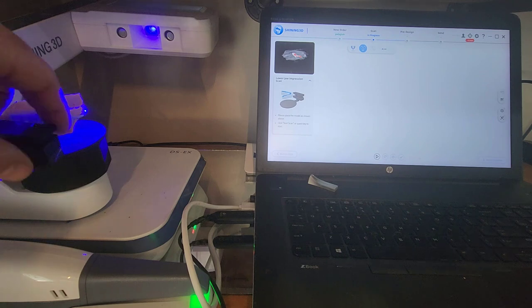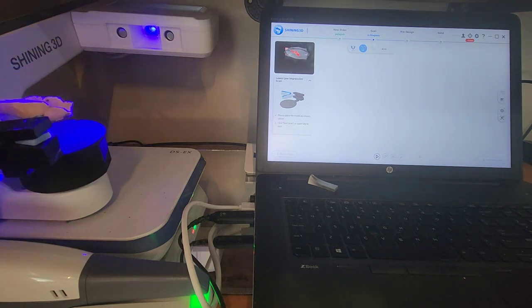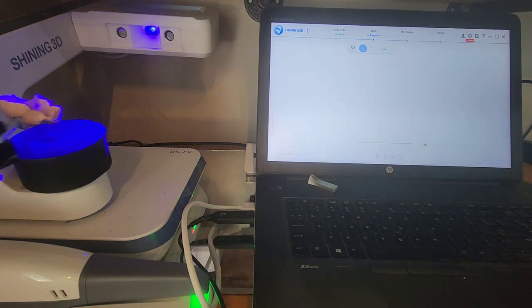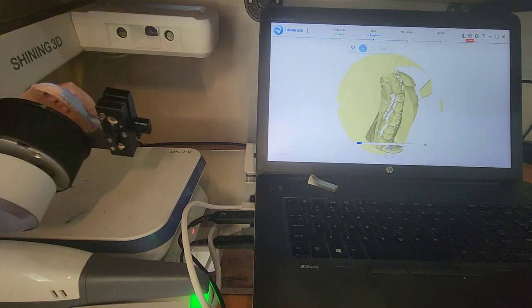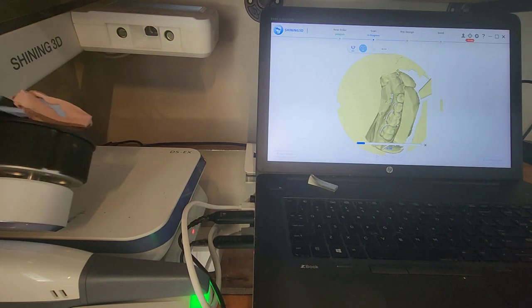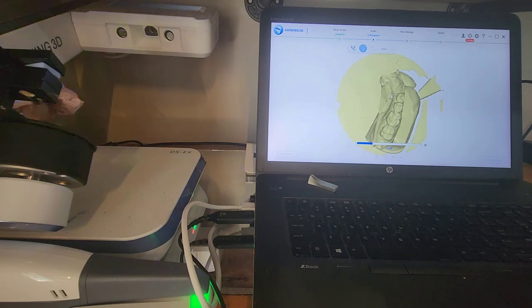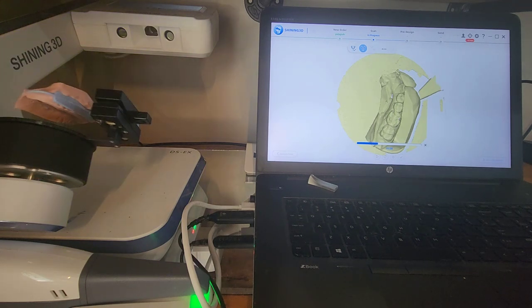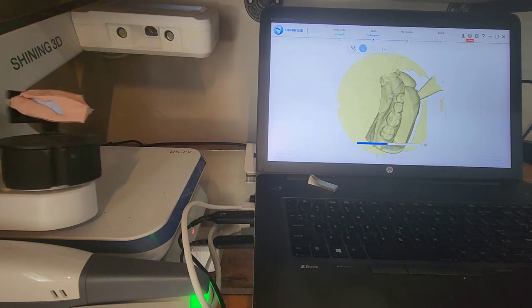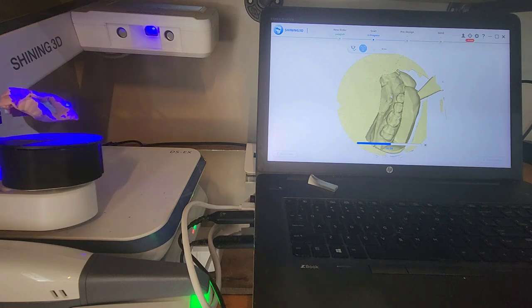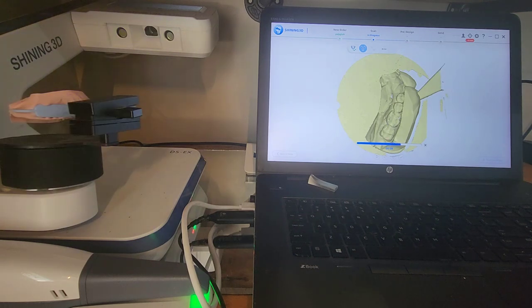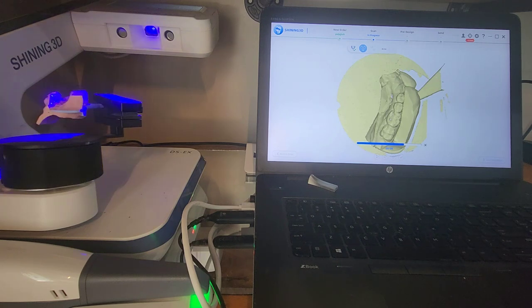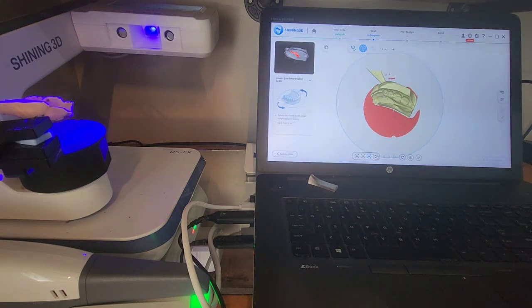Now it wants me to do the lower impressions. So you simply take this, flip it over with the magnetic clip, and now you can hit the Play button again. And so as you see, this one's taking 28 images instead of 35. And so usually it's going to spin it around from the side and take a bunch of images. Then it comes up on an angle, takes another round of images, and then it will look directly into the occlusion and pick up all the occlusal surfaces, incisal edges, and so forth. All right, so images are done. It's processing.